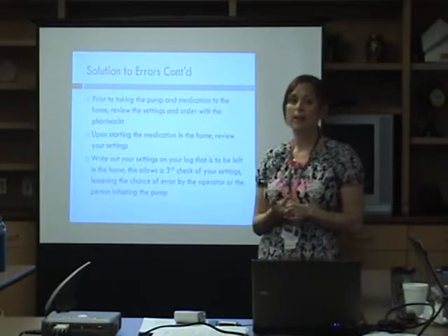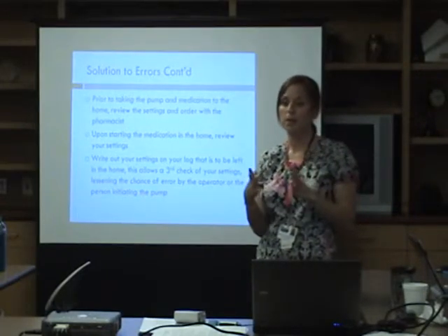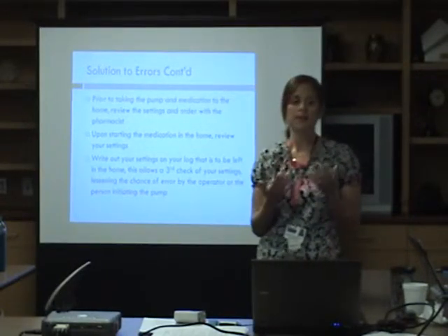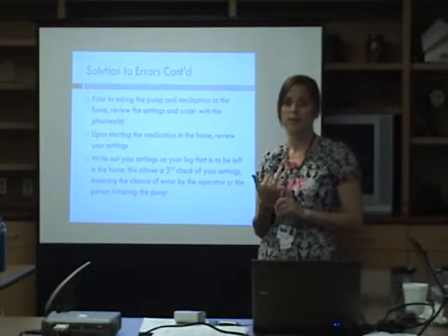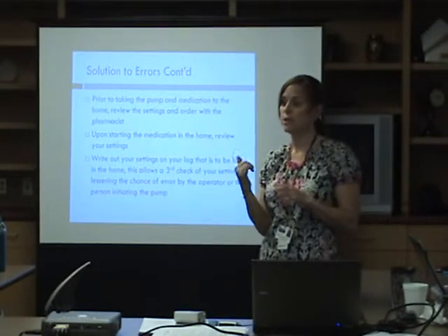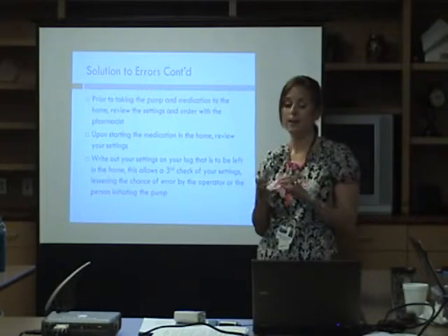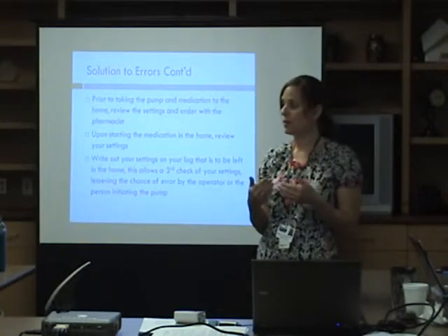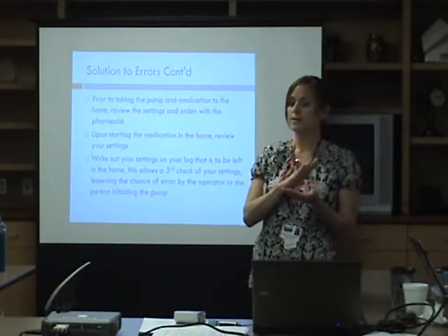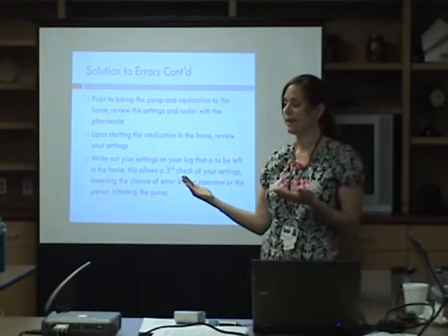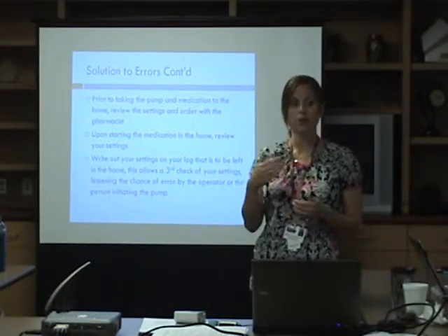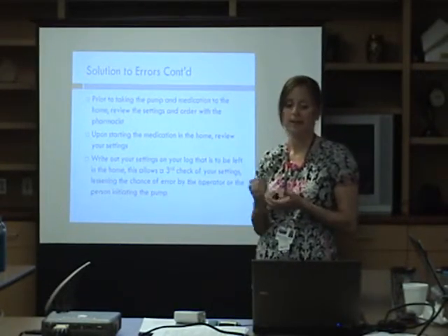The other things that we can do is when you pick up your CADD pump, if you're initiating it, your first check is going over your settings with the pharmacist. That's your first check to make sure your pump is set correctly. When you get in the home and you start the medication, when you hit start, it's going to run through all of the settings. That's your second check of making sure, is my pump set correctly?